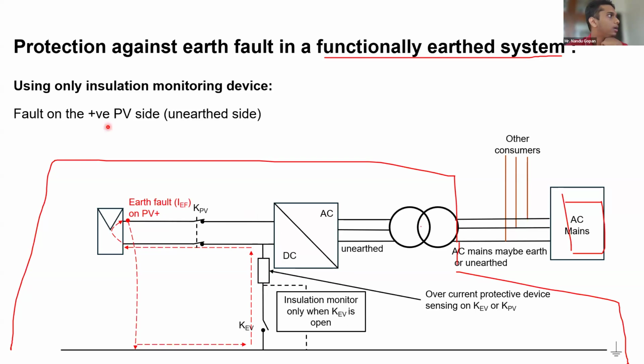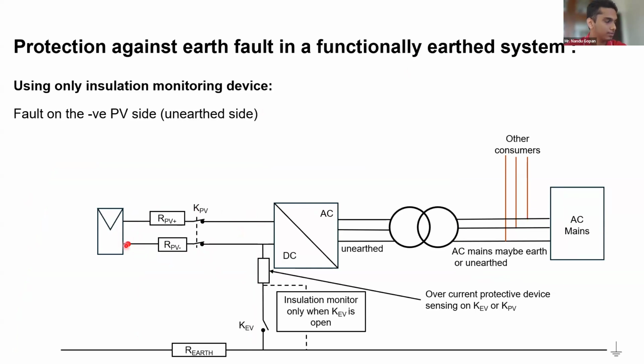In a functionally earthed system, if there's an earth fault on the positive side, that is as described. But if there is an earth fault on the negative side, it can be a little more complicated. For example, this is where the earth fault has occurred. The current will travel like this. The problem is that the earth fault current, IEF, travelling in this path through the functionally earthed system depends on the resistance of the line conductor and on the resistance of the R earth. So if the R earth is high, then the current flowing through this functional earth terminal will be low.